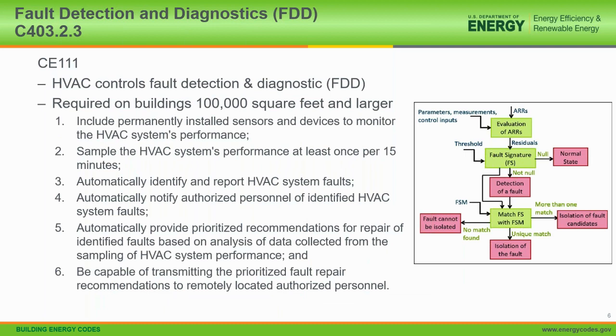CE 111 actually provides for fault detection and diagnostics to be installed in larger buildings. This only applies for buildings over 100,000 square feet in area. Basically, it's an expansion of the direct digital control system that is checking the controls as we go along and makes sure that things are working properly. If it finds an error or suspects an error, it will report out to the DDC system, or send a message to the building operator. So this is expected to improve long-term control operation in larger buildings.